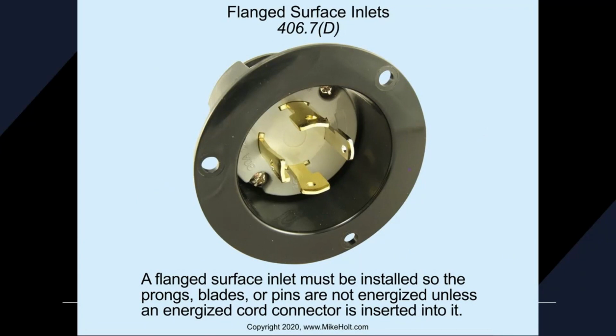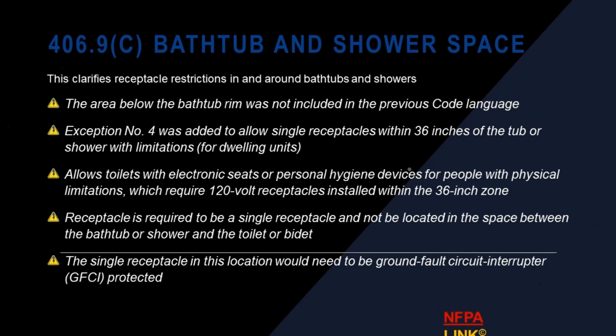Flanged surface inlets. A flanged surface inlet must be installed so the prongs or blades or pins are not energized unless an energized cord or connector is inserted into it. So this cannot be hot and then I plug a female into it. The female has to be hot to charge these male prongs. 406.7.